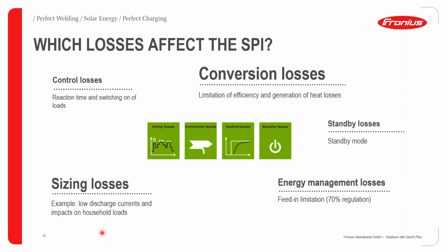The second one being sizing losses. An example of this is low discharge currents and impacts on household loads. So sometimes, for example, when the grid is not available and a very big load comes online, some inverters give you a very low discharge current. So that load can't really come back online, compared with a Symo Gen24 Plus, where we can give you extremely high discharge currents.